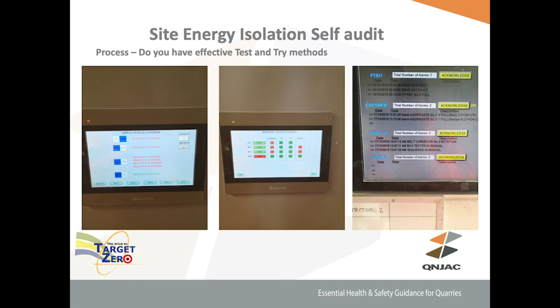At least then you know it's run, you've isolated it, and then you know it hasn't run. Now there will be occasions where a motor or gearbox has gone down and you can't run it. In those instances we have to get the equipment tested by an electrician to prove it's dead. But on most occasions, where we're doing mechanical maintenance work, we'll do a test and try using those touch screens in the switch room.